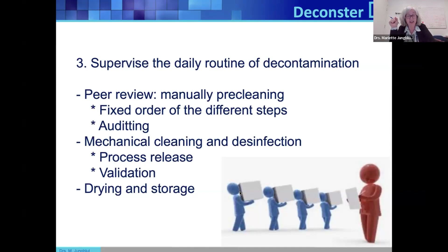Supervising of the daily routine, peer review, as I told you, we have to know the fixed order of the different steps so we can help each other, and auditing at least once a year. Mechanical cleaning and disinfection, process release, whether the machine did the right thing, validation, measuring once a year by knowing the temperature, knowing the concentration, knowing the time, as well for the mechanical cleaning as the drying cabinet, which has to be validated. Next one, please.